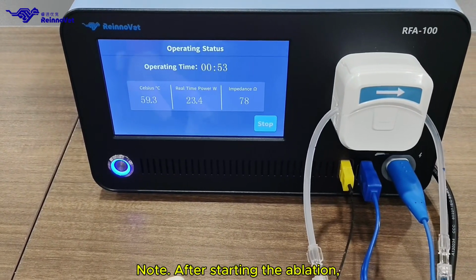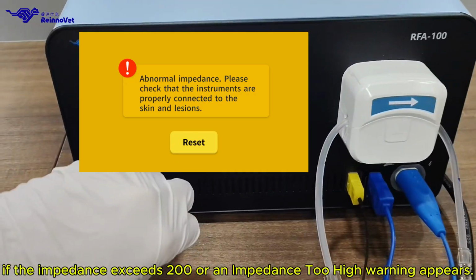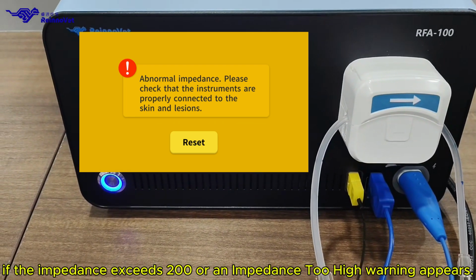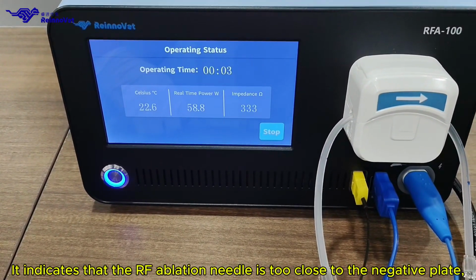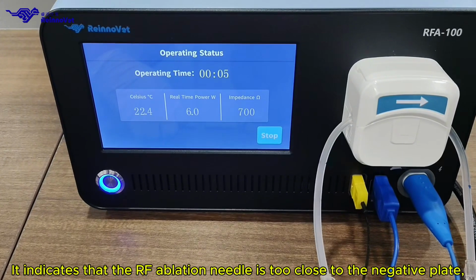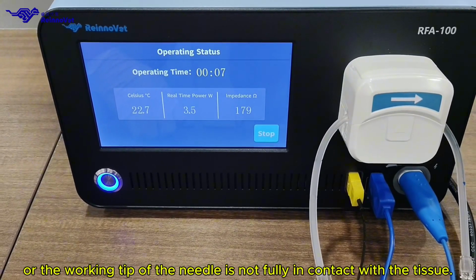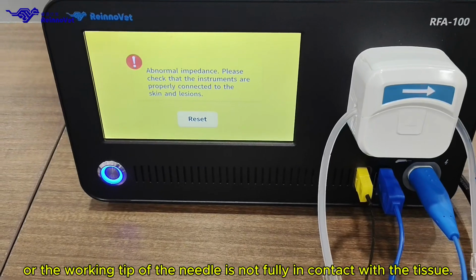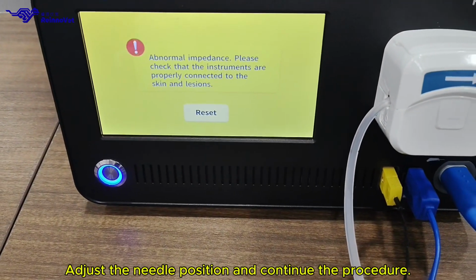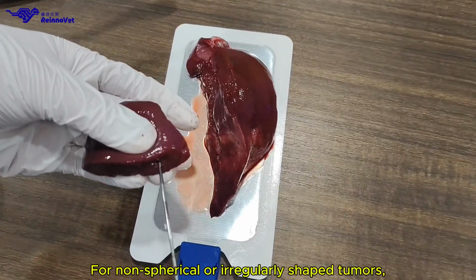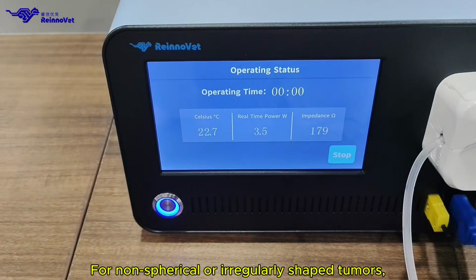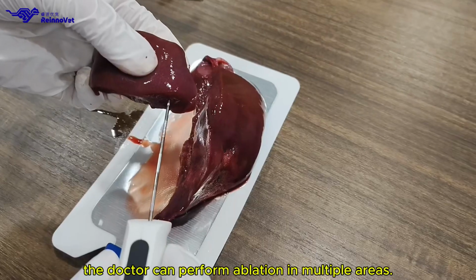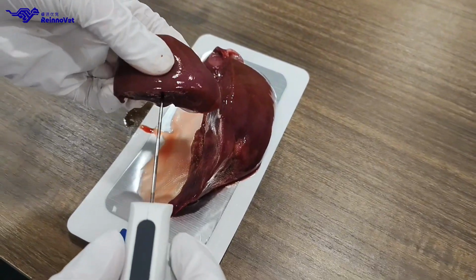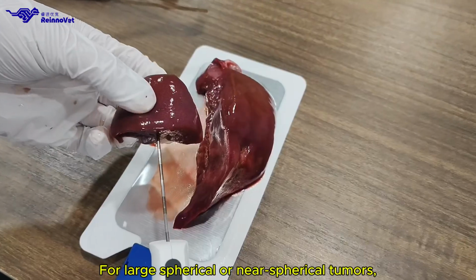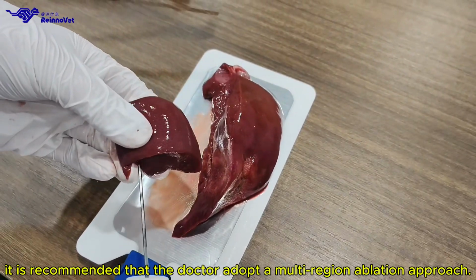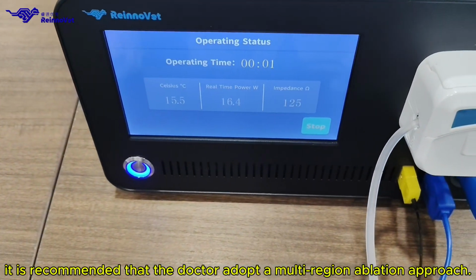After starting the ablation, if the impedance exceeds 200 or an impedance too high warning appears, it indicates that the RF ablation needle is too close to the negative plate, or the working tip of the needle is not fully in contact with the tissue. Adjust the needle position and continue the procedure. For non-spherical or irregularly shaped tumors, the doctor can perform ablation in multiple areas. For large spherical or near-spherical tumors, it is recommended that the doctor adopt a multi-region ablation approach.